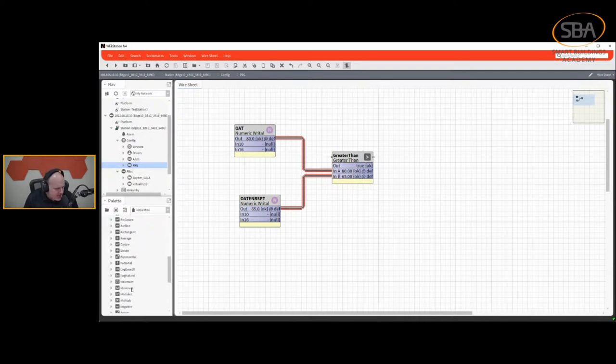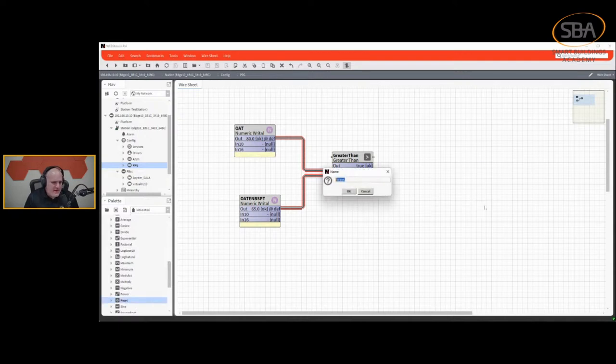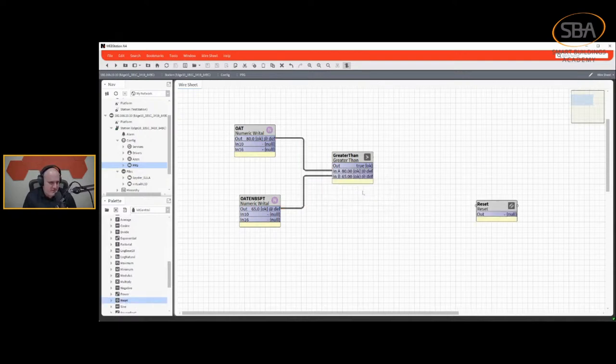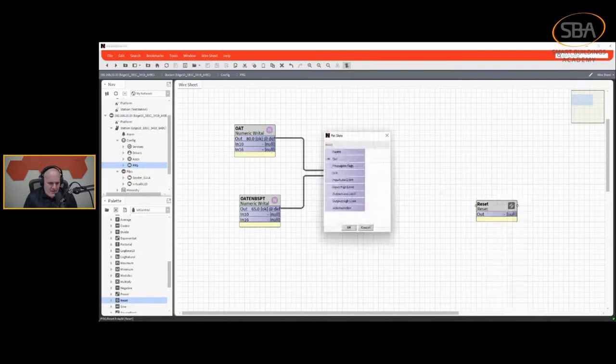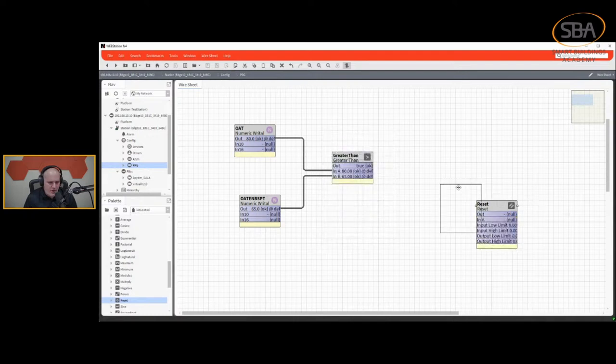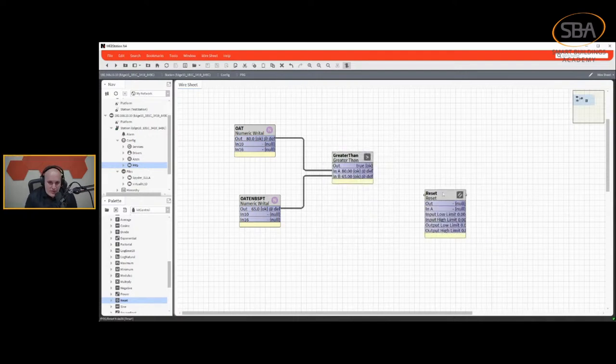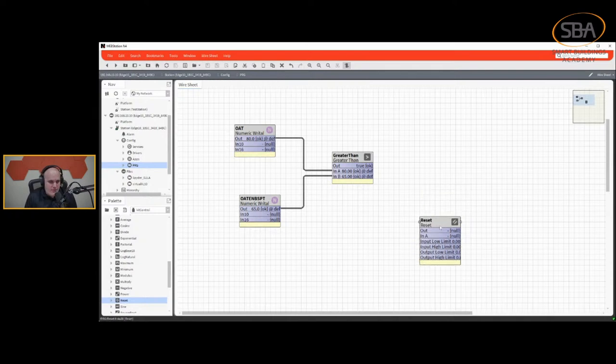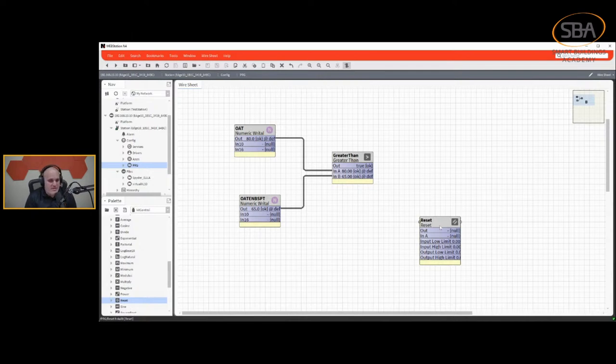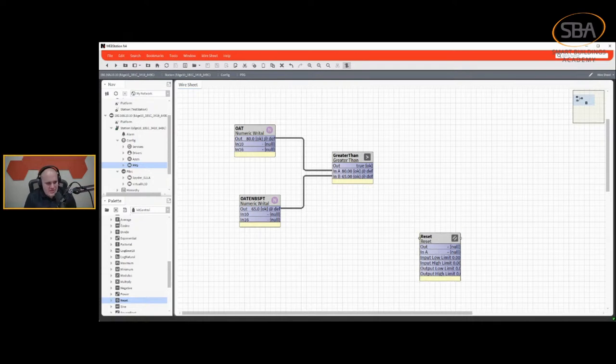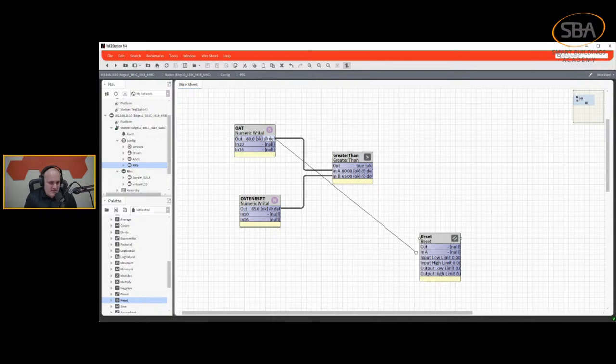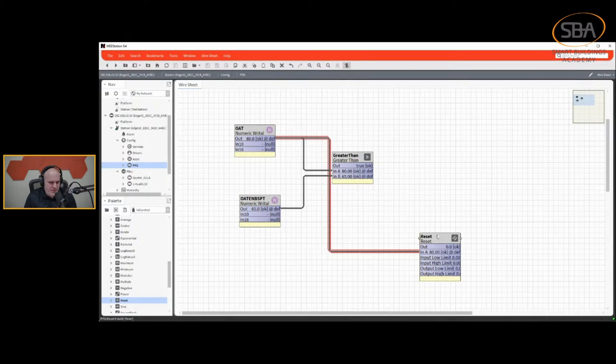Which brings us to our next design pattern, which is going to be called the reset pattern. Now we've seen reset patterns all over the place. So the reset pattern is another pattern that we use all the time. When outside air temp is 30, we discharge 180 degrees on our hot water setpoint. When outside air is 60, our hot water setpoint for our secondary loop maybe is 140 degrees. And this is an example of a reset.